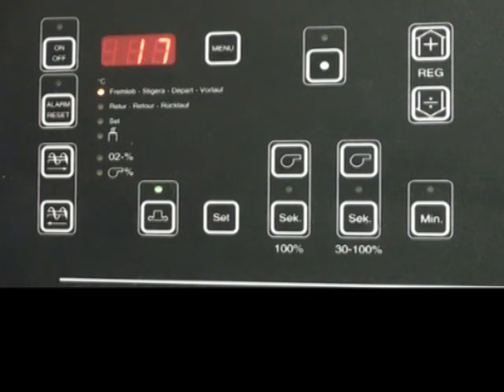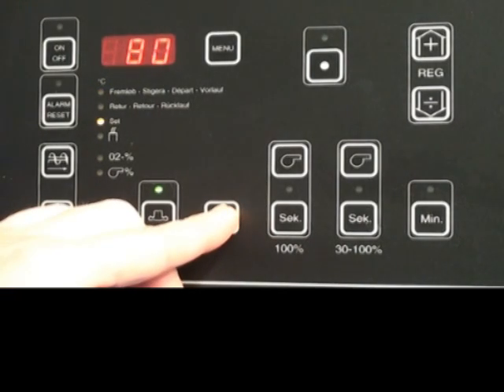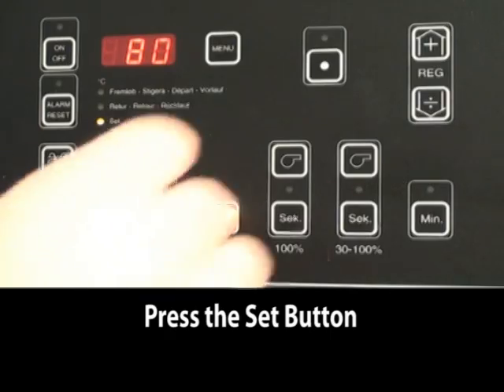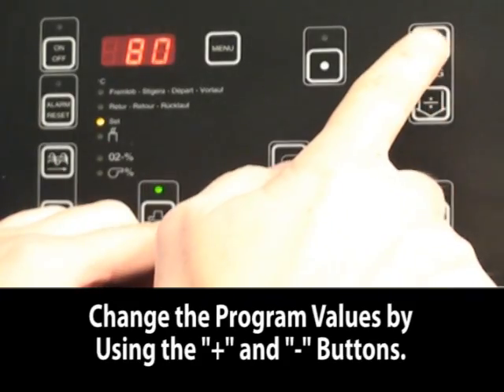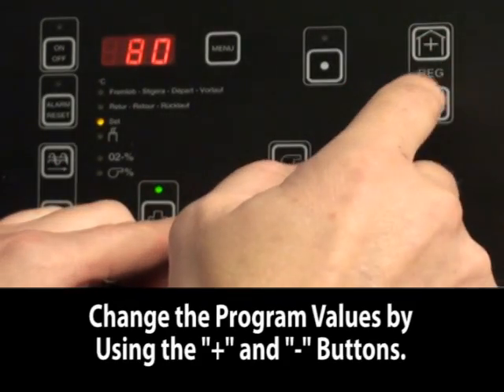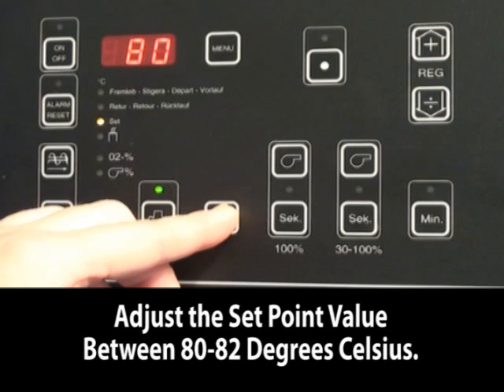To change the set point of the boiler, you hold down the SET button. It gives you the reading, and that can be changed by using the plus or minus button. Typically we want this between 80 and 82 Celsius.